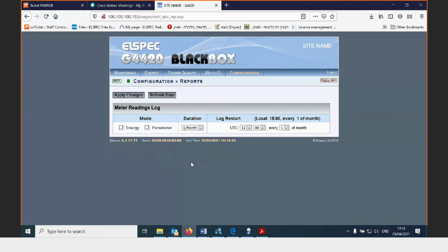It can record only 1 or 2 hours. And I connected by remote session, and in his compact flash, I found a report folder full with many, many, many Excels. And when you have 128 megabyte and there is no FIFO in this, it's consuming the storage and not allowing the PQZip folder to have enough storage.